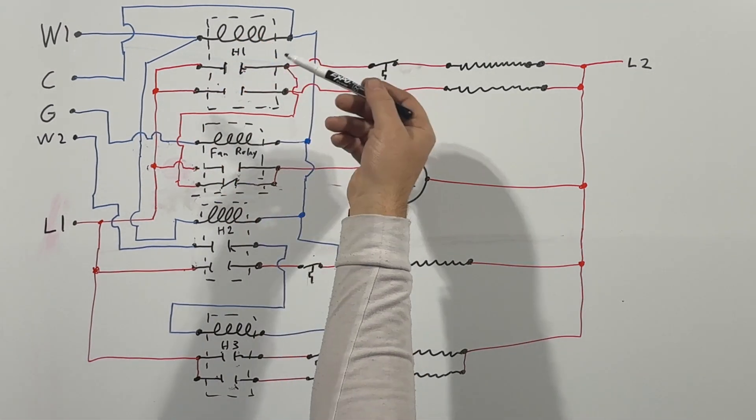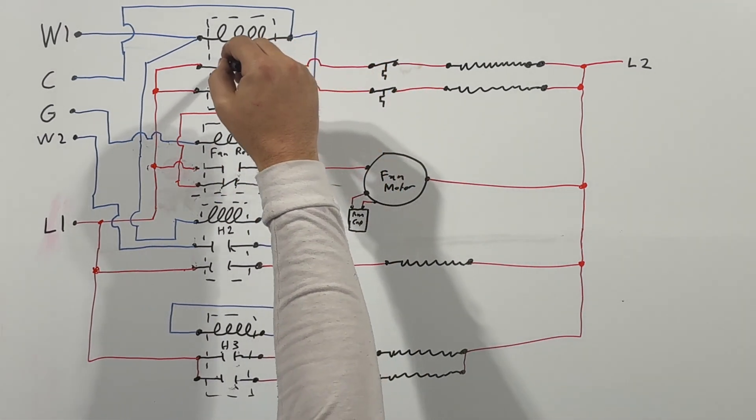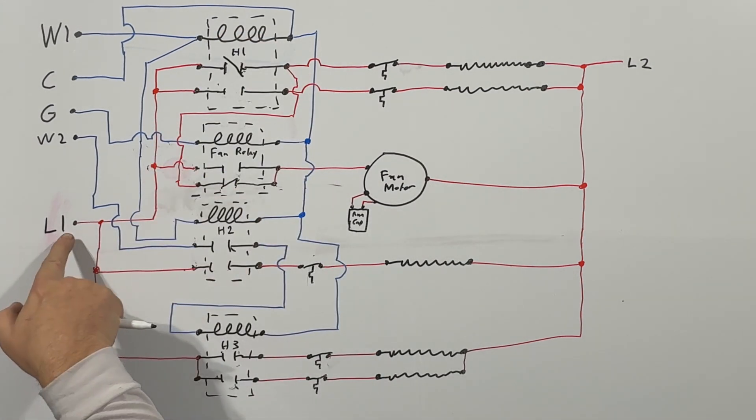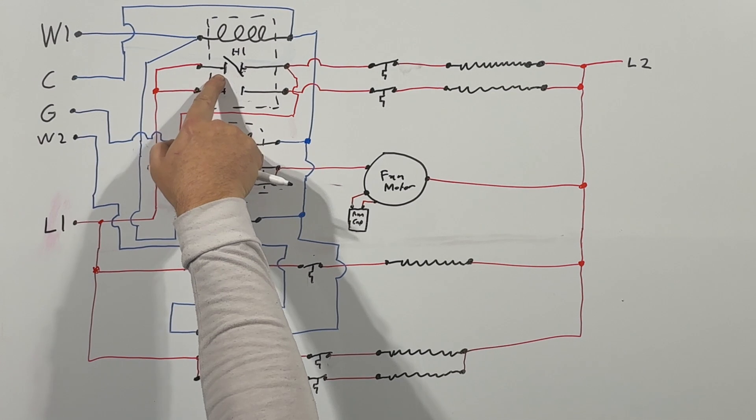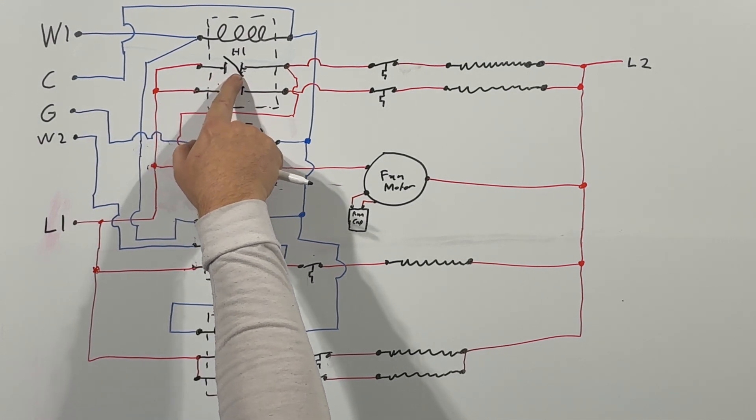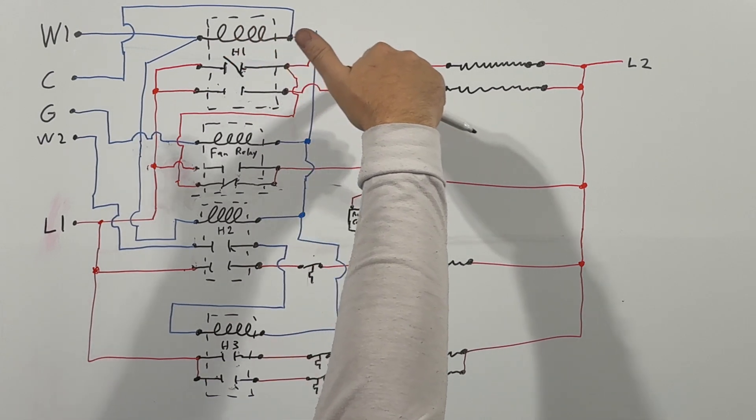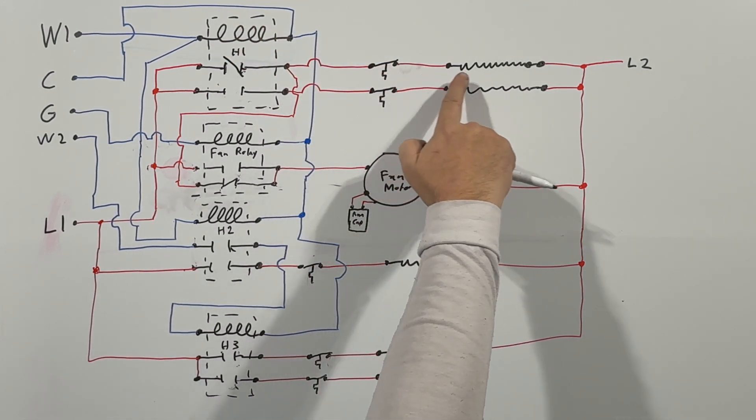So as it warms up, it's going to go ahead and start closing these contacts at different points, at different timings. So this first one is going to close, right? So we have our line one, which travels up here and goes into this first contact. When this closes, the high voltage will move through it and continue on through our high limit and then into our electric strip, which will energize and start heating.